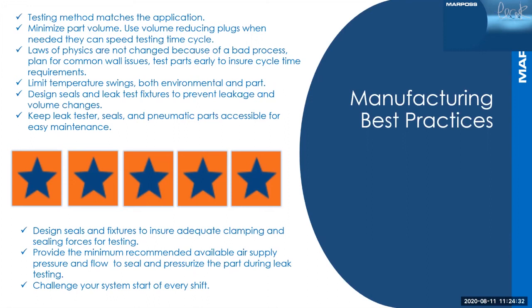And you definitely want to challenge your system every shift. You put in your master part and verify that you get your non-leak reading, your 0. Then you install your leak master and verify that the system rejects that part at the expected leak rate. This lets you know that the system is capable of doing what it's expected to do. We recommend doing that at least once per shift.